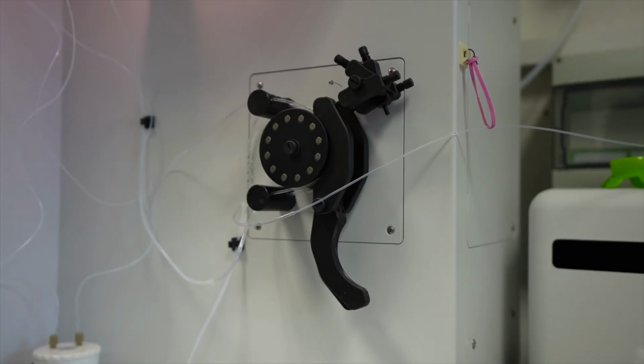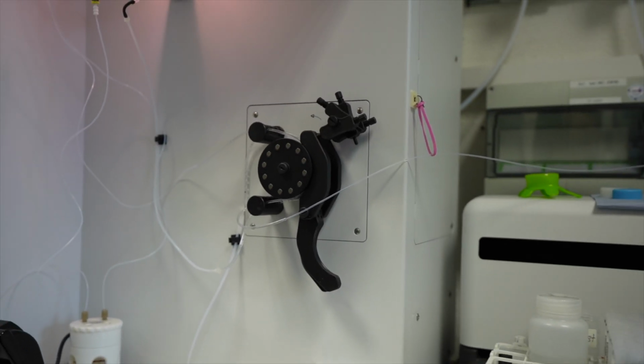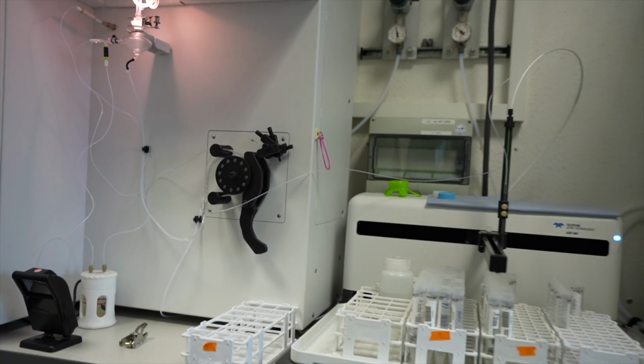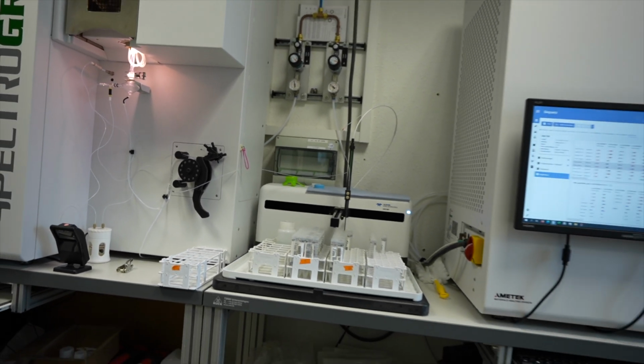Actually the lab, because we are in the middle of the day, it's fully working, but we can have a close look at one of our machines, which is a SPECTRO GREEN, and we have some specific reasons why we choose that type of machine for the seawater testing. For the reverse osmosis or for freshwater testing, we'll use another machine, which is the SPECTRO BLUE. Later, we bought the new one, which is the ICP Green, the machine which I will show you now, which overall gives the best results.